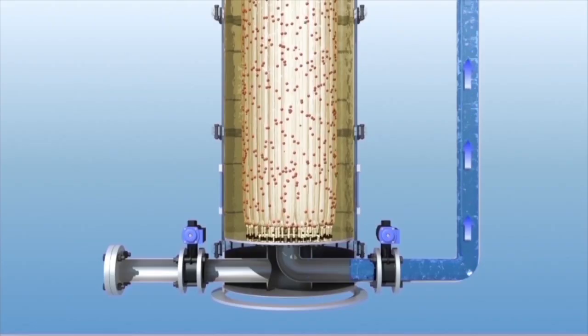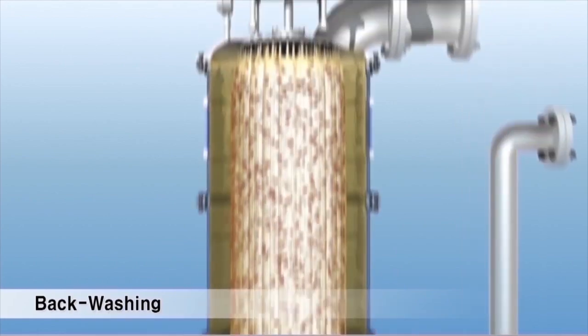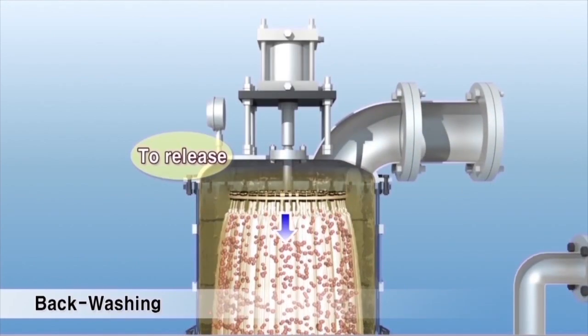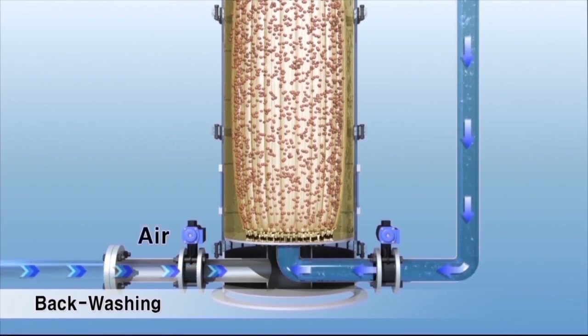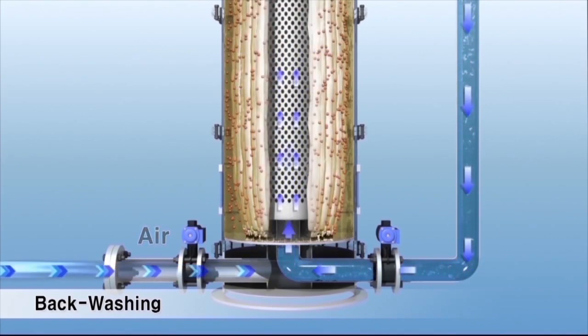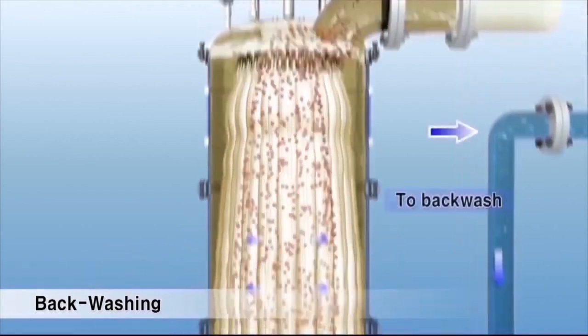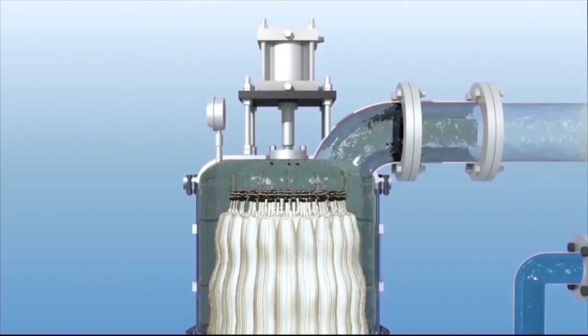It is an air gap controlling filter that filtrates by reducing the air gap and backwashes by releasing and expanding it. Captured SS gets isolated from fiber media by reverse air and is discharged out of the filter by backwashing water.